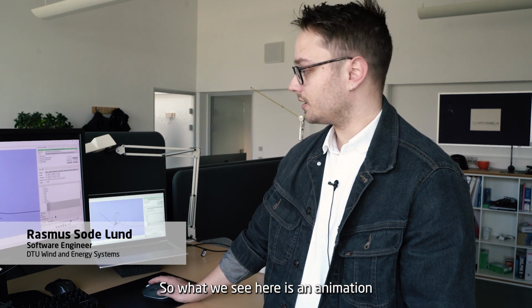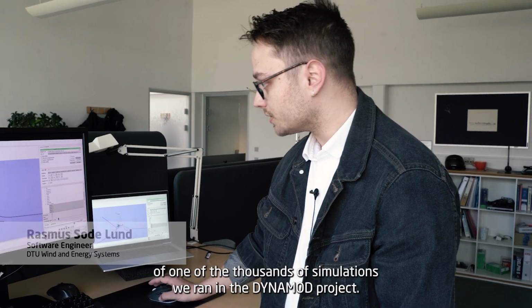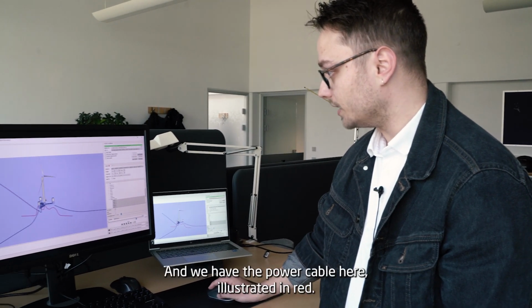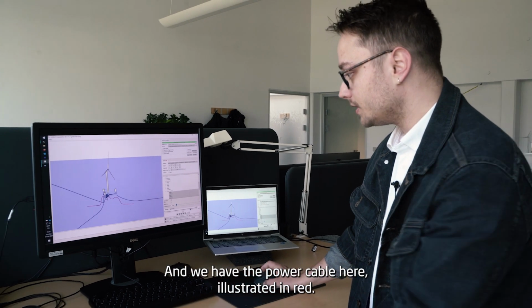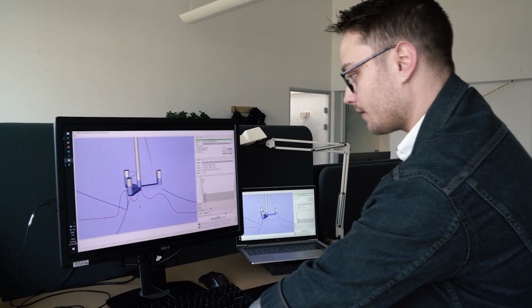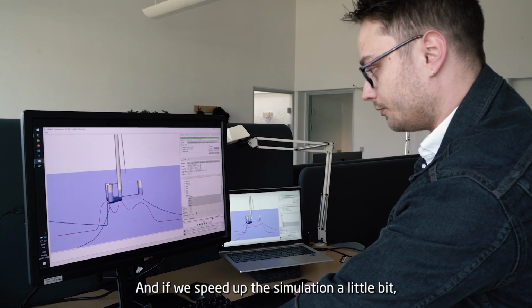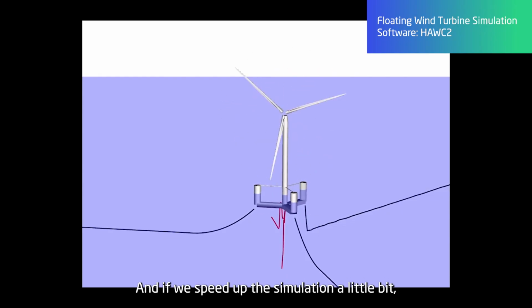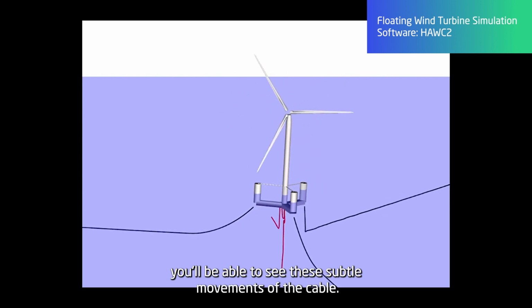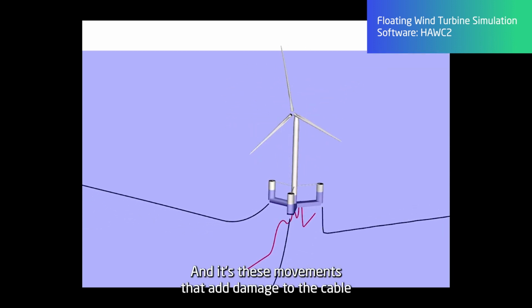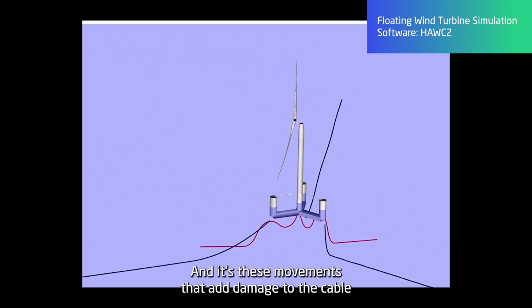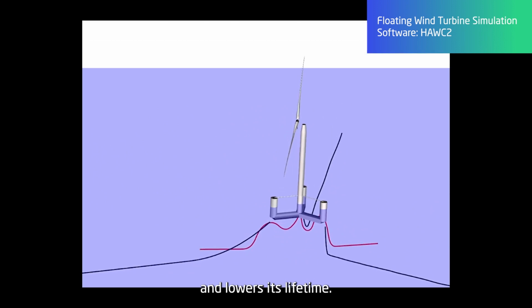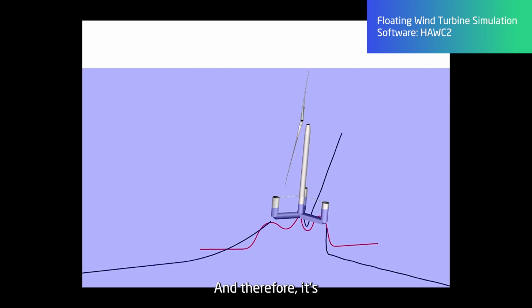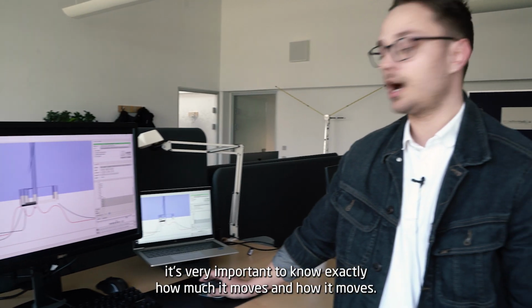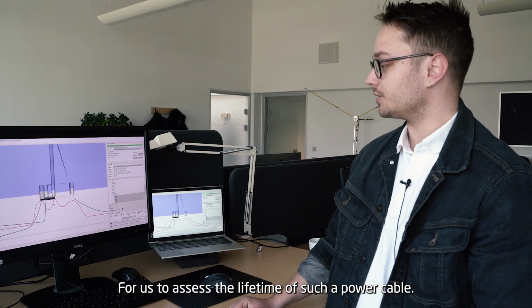So what we see here is an animation of one of the thousands of simulations we ran in the DYNAMOD project. And we have the power cable here illustrated in red. And if we speed up the simulation a little bit, you'll be able to see these subtle movements of the cable. And it's these movements that add damage to the cable and lowers its lifetime. And therefore it's very important to know exactly how much it moves and how it moves for us to assess the lifetime of such a power cable.